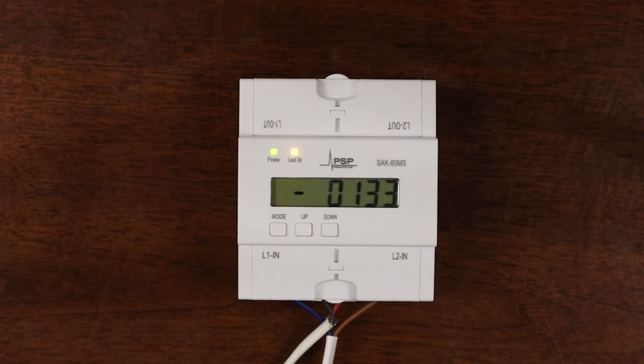Here I have the SAK60MS connected to a CT simulator to demonstrate its operation. I have the high current set point set at 160 amps and the low current set point set at 115 amps.